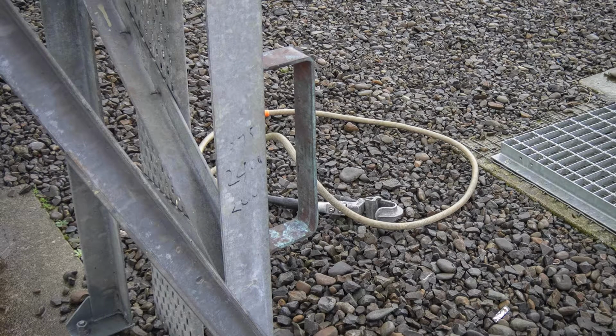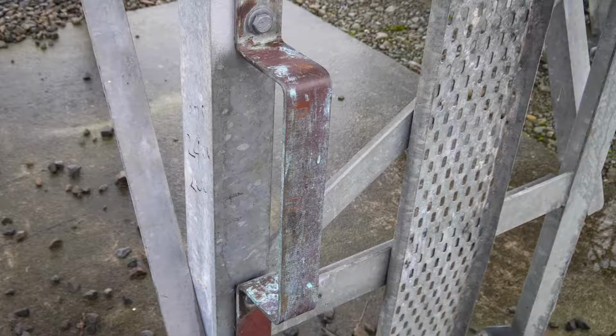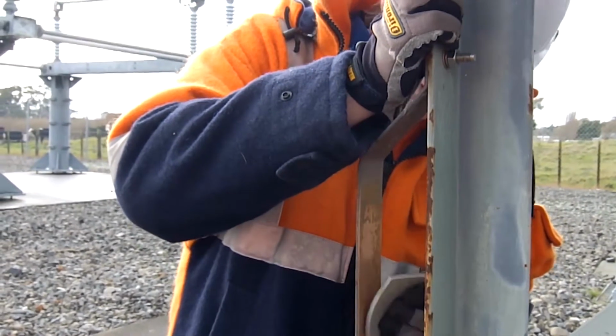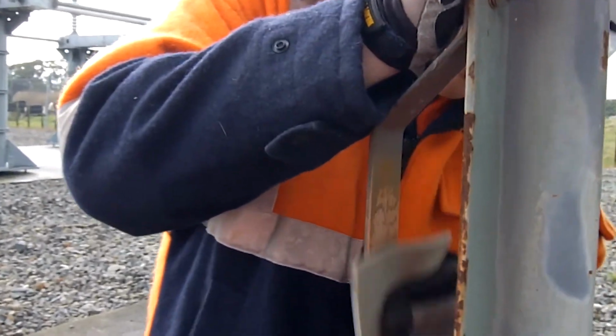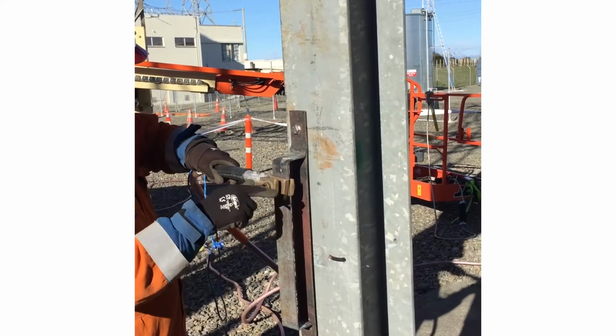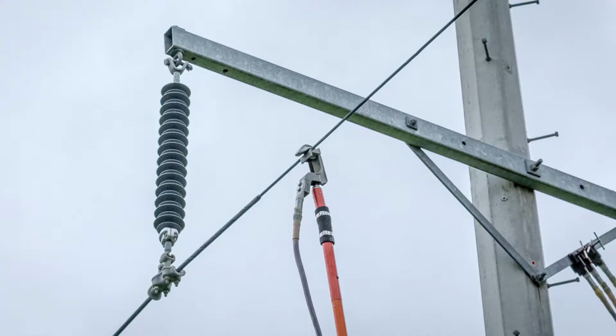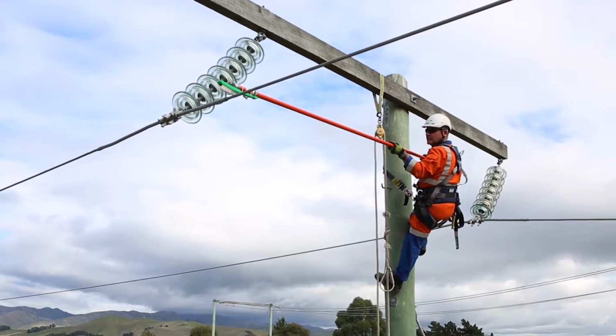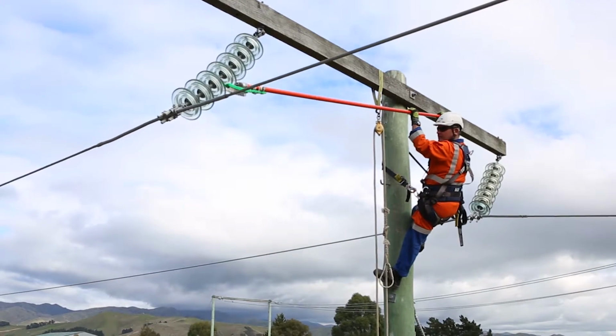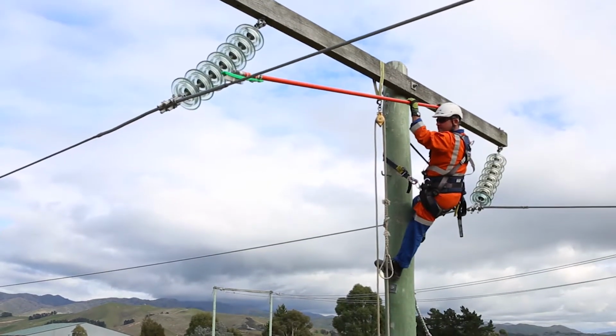Cleaning earth attachment points is also important if you are working in a substation. Copper Ds can be easily cleaned by hand using a Scotch-Brite pad or mildly abrasive products. Make sure you clean the correct side, which is the inside surface. Otherwise, you won't have two clean surfaces in contact when attaching your tail clamp. Now let's look at the live end connections. Once your tail clamp is clean and attached, you need to make sure that all of the surfaces on the other end are clean too.